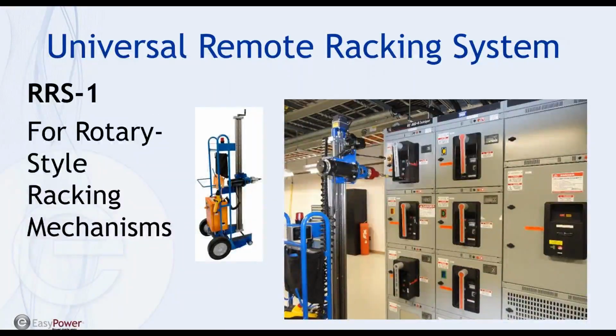This is an example of the RRS1, again, remote racking system, the original product from CBS ArcSafe. It works on slides and can move up. There's a motor option where it can move itself up to certain heights, I think up to 4 cabinets high. You'll have attachments that go in and attach to the racking mechanism on the breaker, then that lines up with the motor, and it'll rack any rotary style circuit breaker that's commonly available. Nice solution.